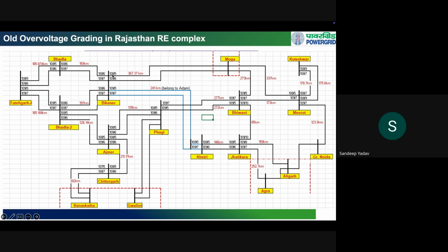So if the voltage goes beyond 108% of the rated voltage and stays for 5 seconds, circuit 1 will be tripped. There was not enough margin, not enough grading between the circuits. Most of the circuits were graded at 5 seconds, 6 seconds and 7 seconds only. Because there was not enough margin in the entire region, whenever there was an over voltage condition, circuit 1 would trip in 5 seconds, the other circuit in 6 seconds, and then the other lines with a time delay of 7 seconds, they all trip. Most of these transmission lines start tripping one by one within 7 seconds.